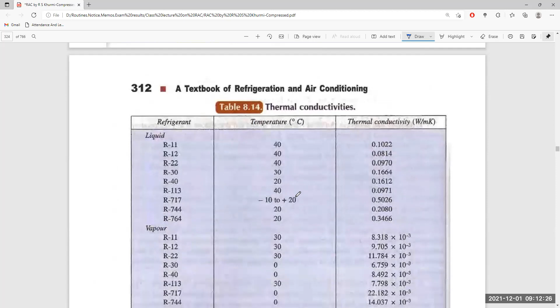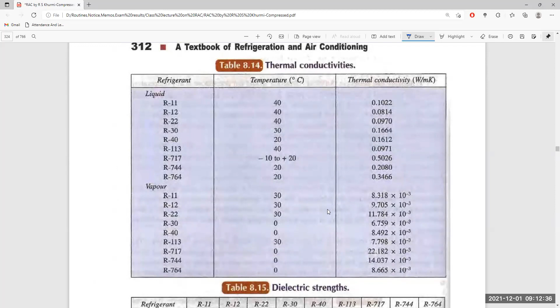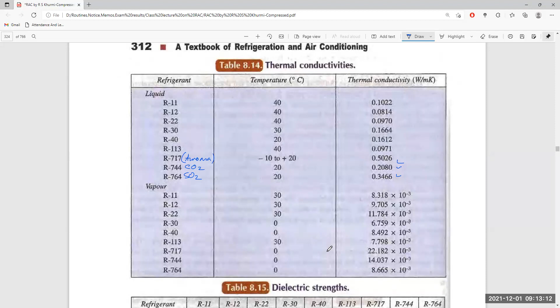Here again, thermal conductivity is in watt per meter per degree Kelvin. Here you see the maximum thermal conductivity is around R717, which is nothing but ammonia. R744 is CO2, R764 is SO2. All of them are highly thermally conductive in comparison to all the freon-based refrigerants, in the liquid state as well as in the gaseous state.